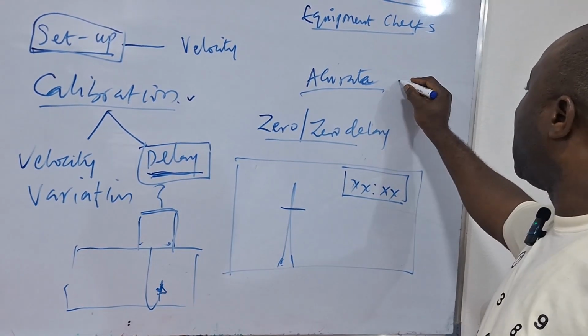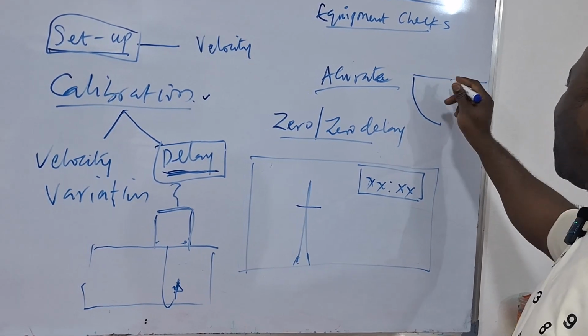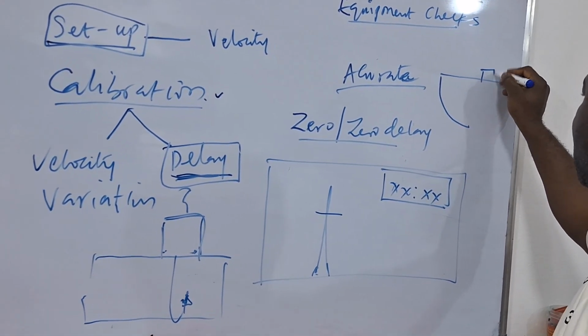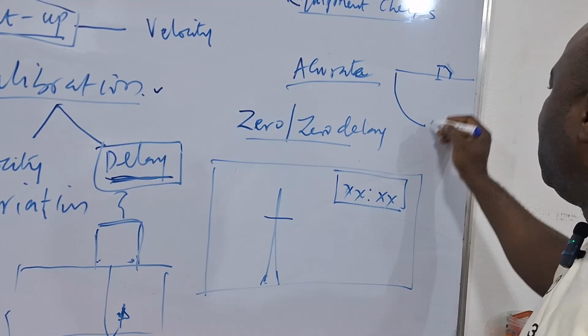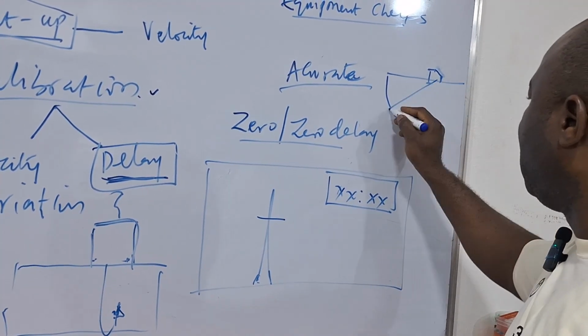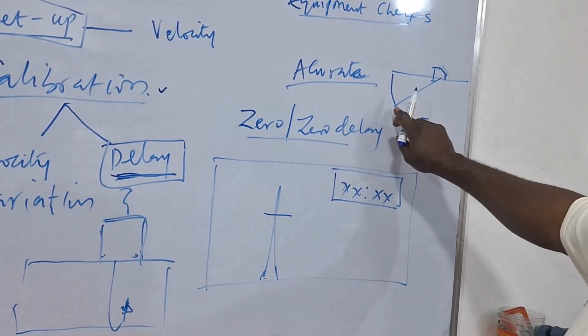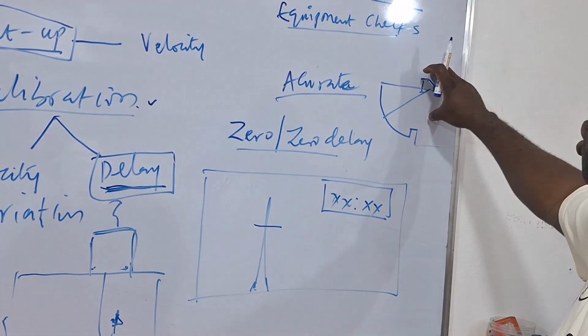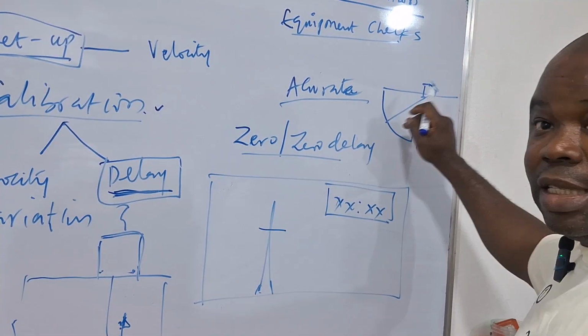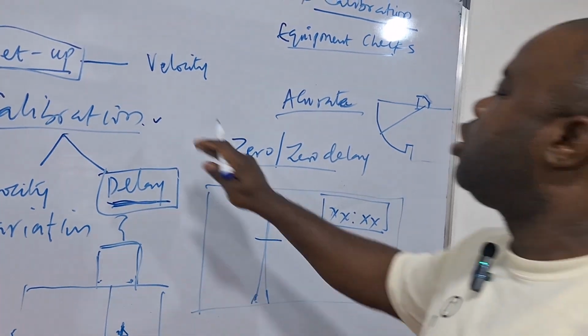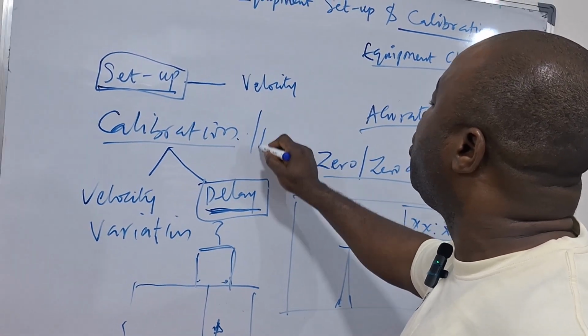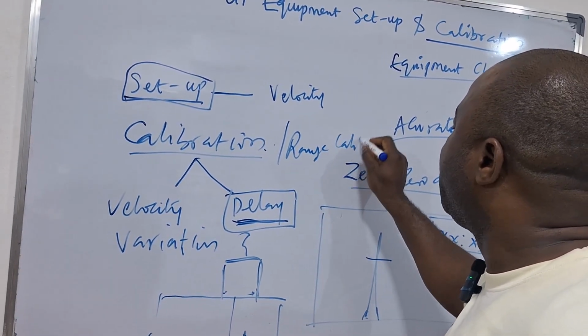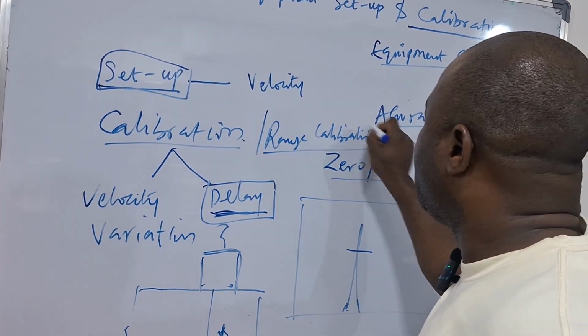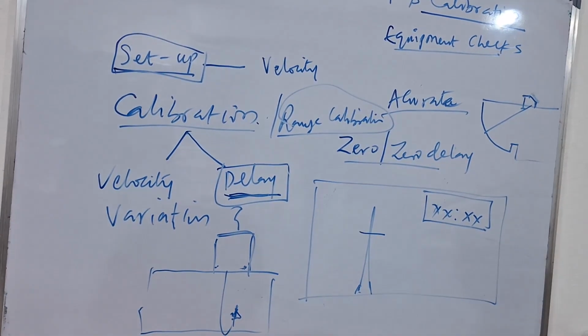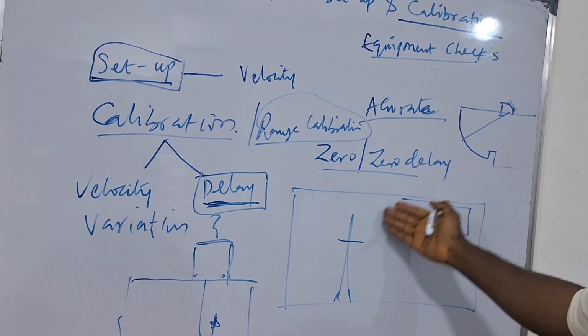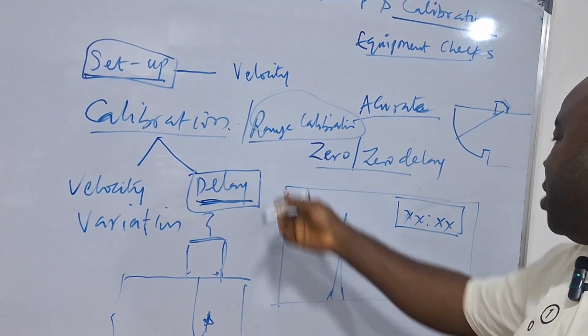If you are calibrating for an angle probe, you definitely need to have a curved surface. If this is your probe, you need a curved surface, whatever the shape is, but it should be curved, and this will give you your known distance. So in some books, instead of calling it calibration, they will call it range calibration. We will talk about this subsequently in this video. So this is what we do when we do calibration.